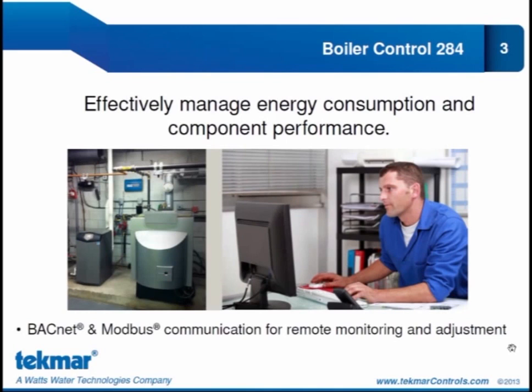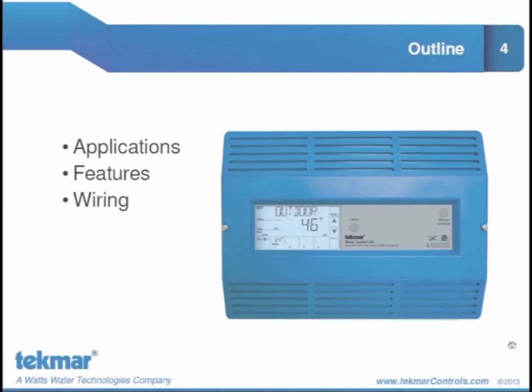The 284 is a designer series multi-staging boiler control that is able to integrate with building automation systems using BACnet IP or Modbus. It provides building managers with the ability to remotely monitor and even adjust the heating system, which is an important feature in today's market. The 284 does not replace the 274, 275, or the 265, but it does provide the same staging capability, but with increased functionality and additional features.